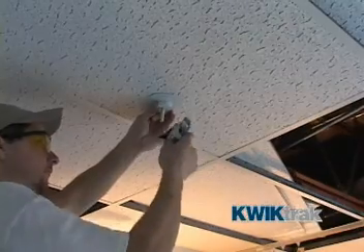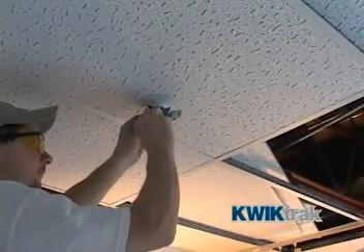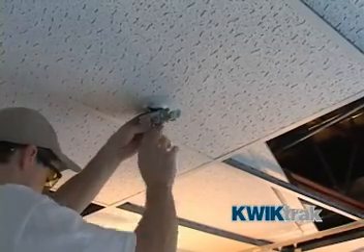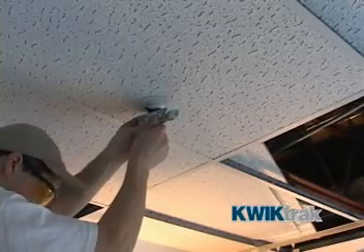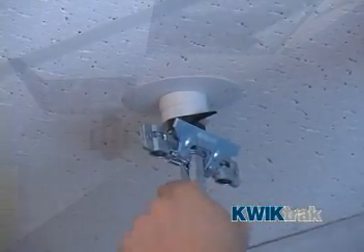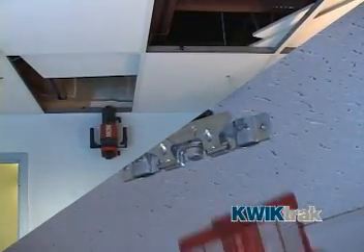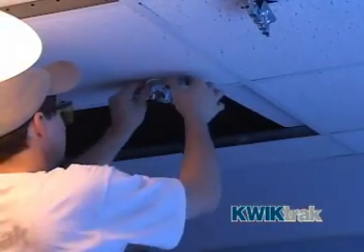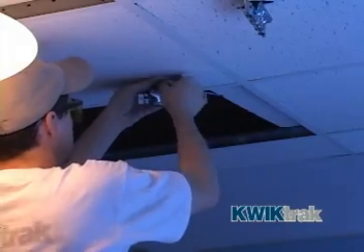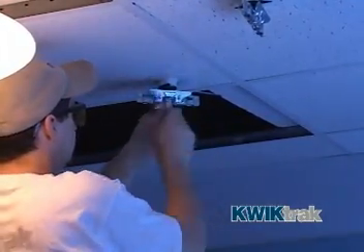Cover plates, shims if required, and ceiling brackets are secured to the threaded rod using washers and lock nuts. A rotary laser is used to level the bracket and determine the degree of shimming each may require for the track to be set perfectly level.